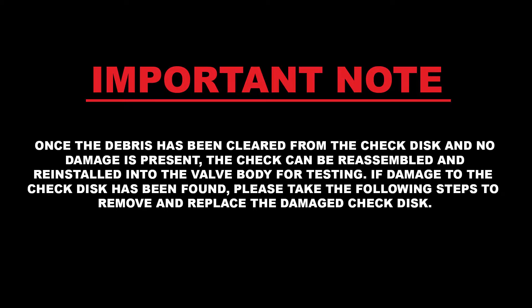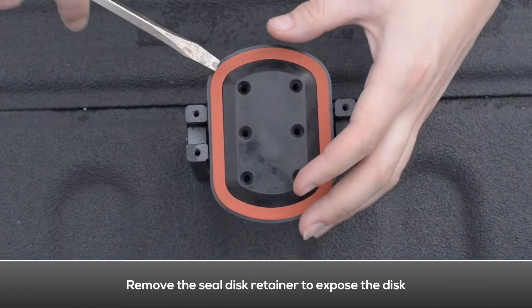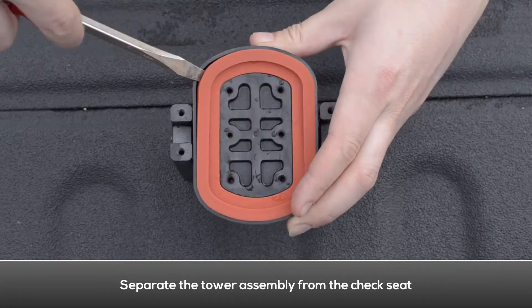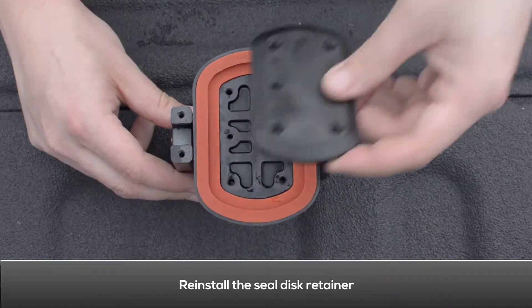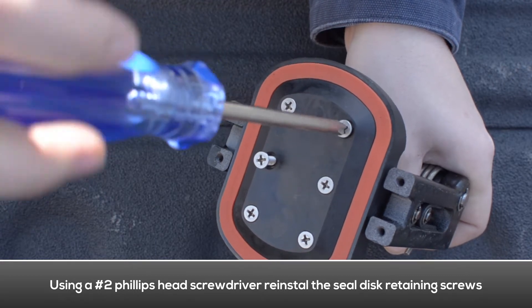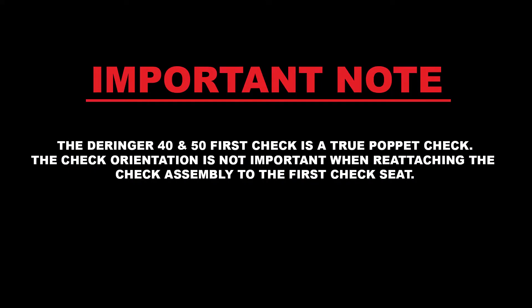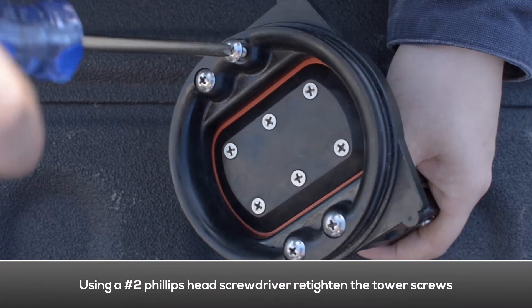Once the debris has been cleared from the check disc and no damage is present, the check can be reassembled and reinstalled into the valve body for testing. If damage to the check disc has been found, please take the following steps to remove and replace the damaged check disc. Using a Phillips head screwdriver, remove the seal disc retaining screws. Remove the seal disc retainer to expose the disc, then remove the seal disc. Install the new seal disc and make sure it is completely flat inside the check cavity. Reinstall the seal disc retainer. Note that the Derringer 40 and 50 first check is a true poppet check — orientation is not important when reattaching the check assembly to the first check seat. Reattach the tower assembly and re-tighten the tower screws using a Phillips head screwdriver.